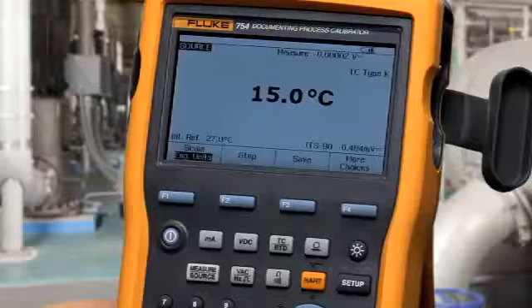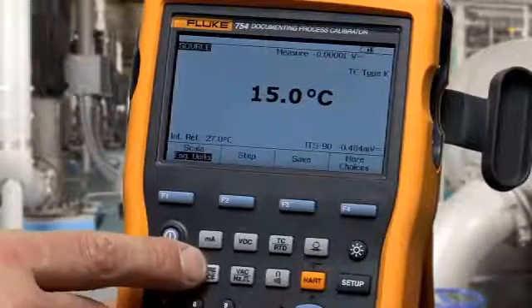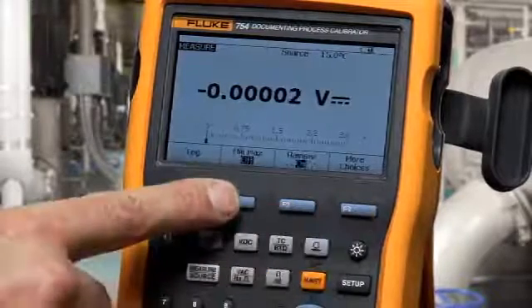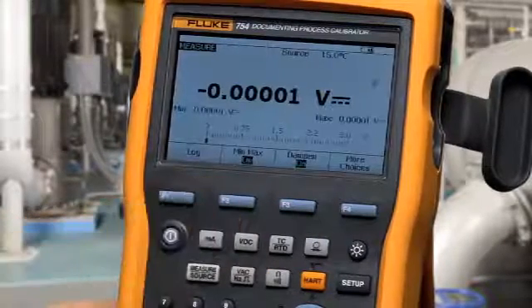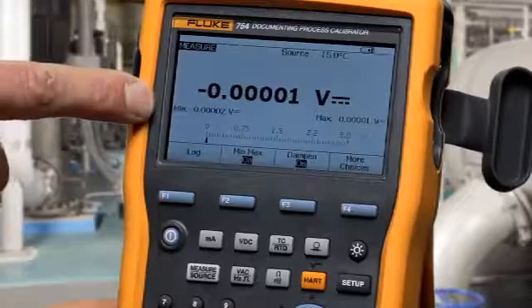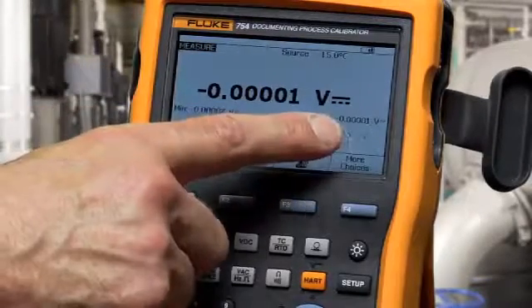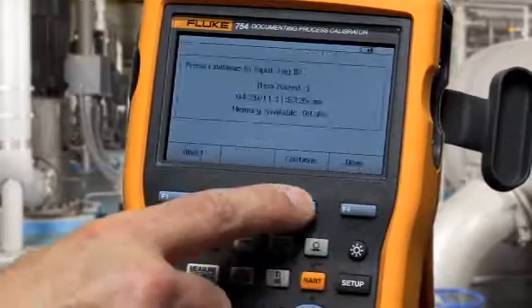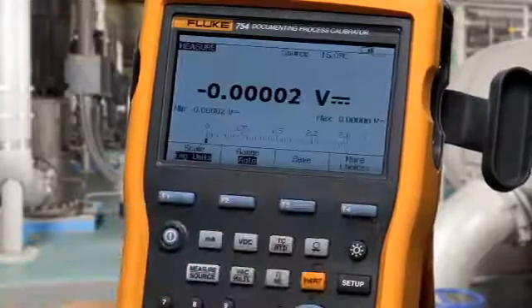To make min-max measurements, select the measure screen, press more choices two times, and then select min-max. The calibrator will capture the minimum measured value, the maximum measured value, and if you want to save to memory, press more choices and save, and then that information is stored in memory.